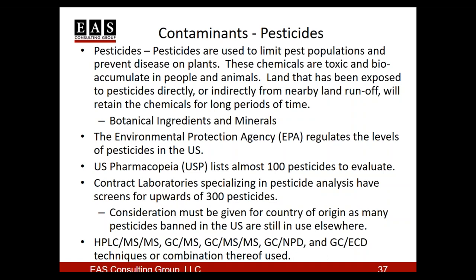These are usually very low levels, and there can be lots of them. If we're looking for 300 different pesticides, we need sophisticated instrumentation—usually a combination of equipment, such as an HPLC with two mass specs (triple quad), a GC mass spec, or a GC with two mass specs. We can also use NPD or ECD for pesticide analysis. Often a combination of these techniques is used to determine all 100 or 300 pesticides in a full screen.